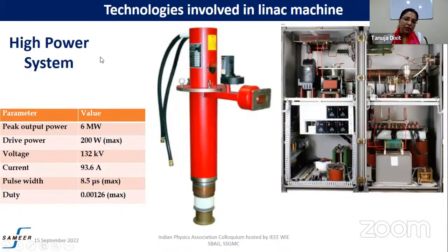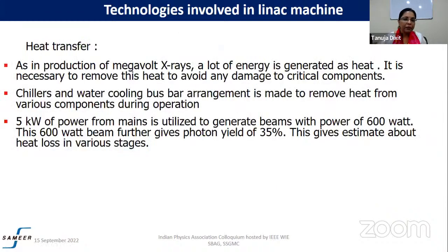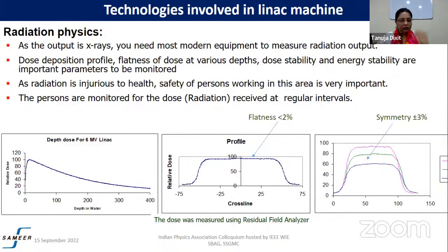This is a picture of our klystron, which we use in our 15 MeV systems. The power requirement is 6 megawatts to achieve 15 MeV energy in the accelerating structure. A lot of power goes into these components, and this power gets dissipated across various parts, so we have to take the heat out. A lot of chillers and other systems are required for this.